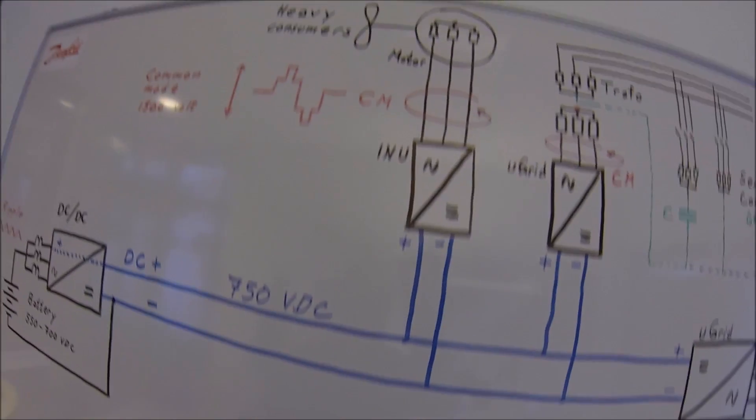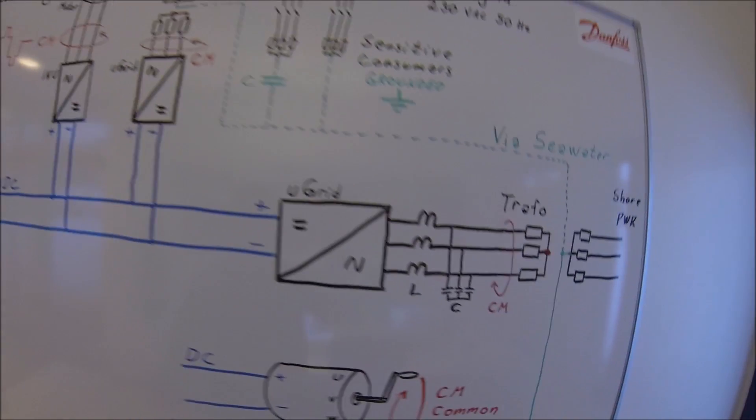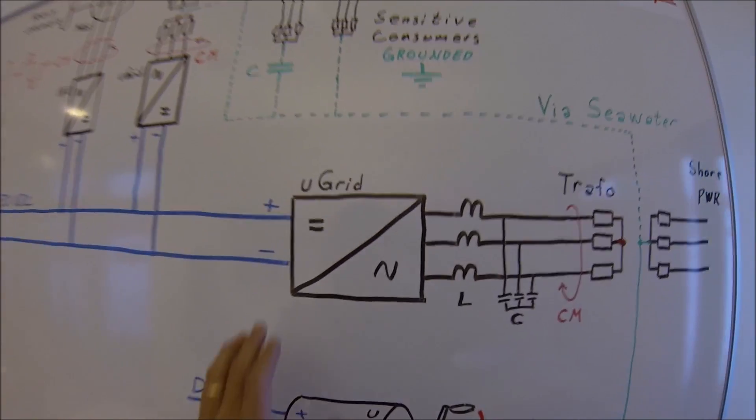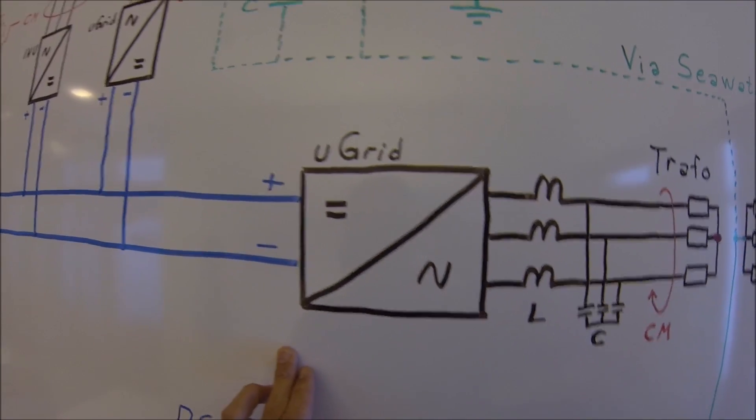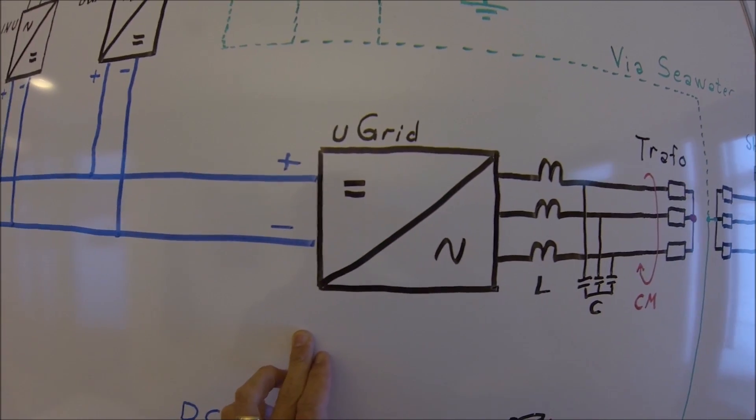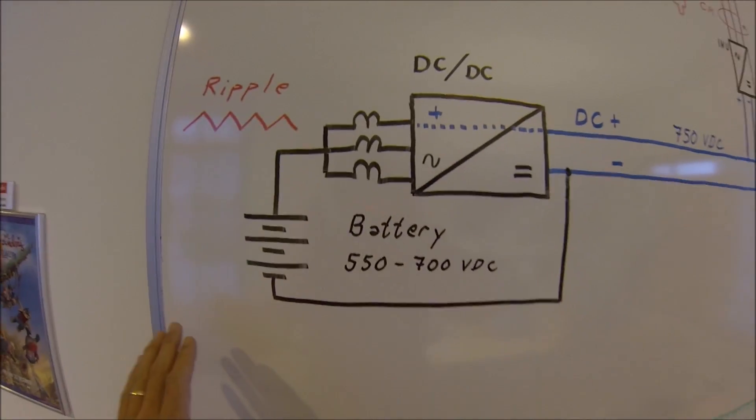However, there are many other consumers on board in a hybrid ship that can make common mode, especially the charger. There is a big frequency converter that usually is connected to shore that is supposed to be able to charge the big batteries.